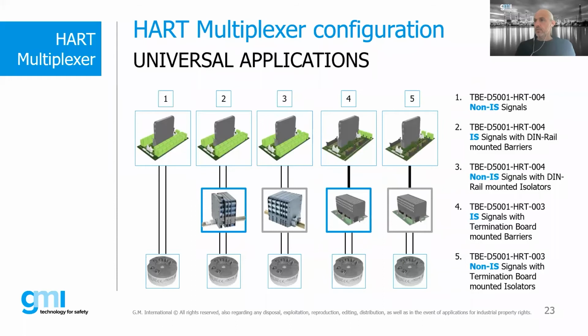We want to recap. We have the first solution, where the non-IS signal is connected directly to the termination boards in and out. The second one is the IS signal connected with barriers. You can also have this architecture. The third is the non-IS signal, where in this case the isolators are non-IS, just simple isolators, not for hazardous areas. The fourth is the application with IS signal, but using termination boards. And the fifth is the same solution, but for non-IS signal. So you can have multiple applications on your system, and you can decide what is necessary, of course.